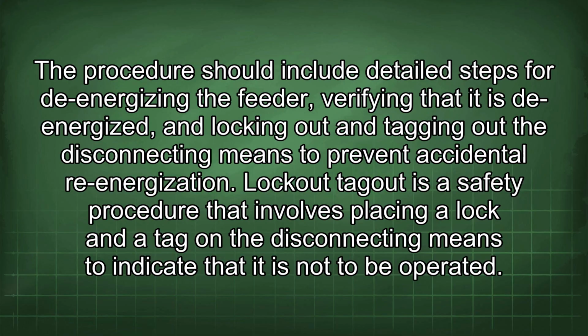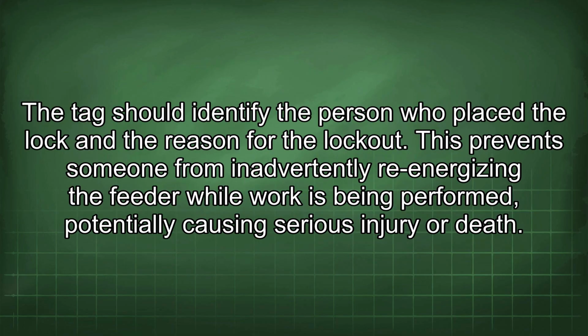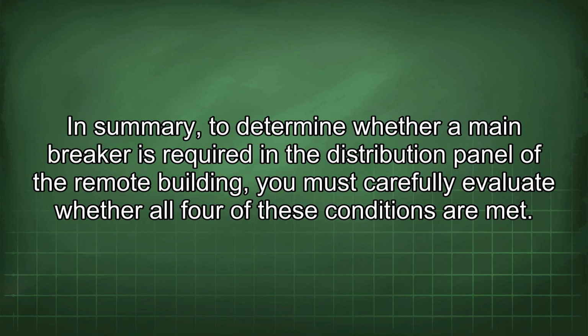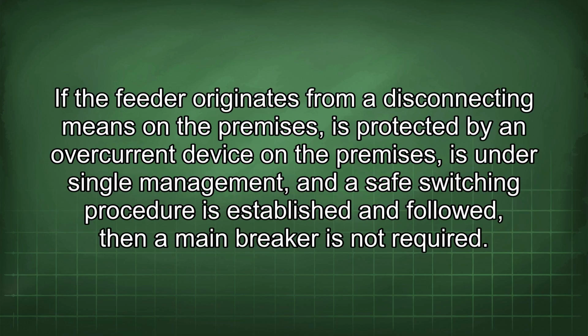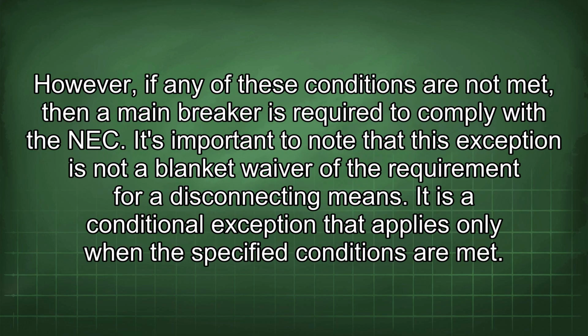Lockout-tagout is a safety procedure that involves placing a lock and a tag on the disconnecting means to indicate that it is not to be operated. The tag should identify the person who placed the lock and the reason for the lockout. This prevents someone from inadvertently re-energizing the feeder while work is being performed, potentially causing serious injury or death. In summary, to determine whether a main breaker is required in the distribution panel of the remote building, you must carefully evaluate whether all four of these conditions are met. If the feeder originates from a disconnecting means on the premises, is protected by an overcurrent device on the premises, is under single management, and a safe switching procedure is established and followed, then a main breaker is not required. However, if any of these conditions are not met, then a main breaker is required to comply with the NEC.